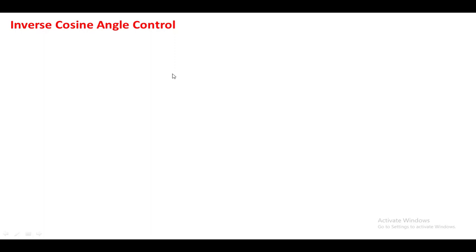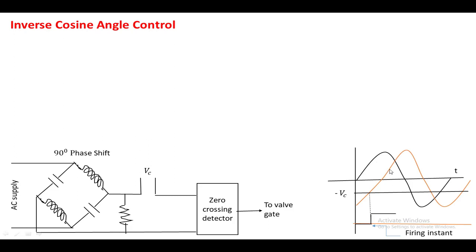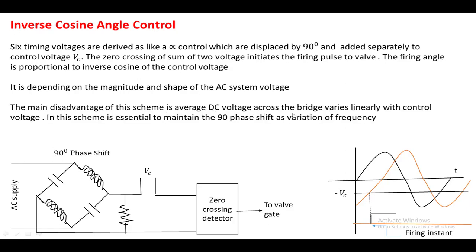Inverse cosine angle control is almost similar to constant alpha control. The only difference is that the six line voltages generated via the transformer through the buses before the converter are shifted by 90 degrees, and that shifted voltage is added to the control voltage. Whenever this shifted voltage intersects the control voltage, the firing angle pulse is generated. The firing angle depends upon the magnitude and shape of the AC voltage. The main disadvantage of this scheme is that the average voltage across the bridge varies linearly with the control voltage, and it is essential to maintain the 90-degree phase shift as frequency varies.